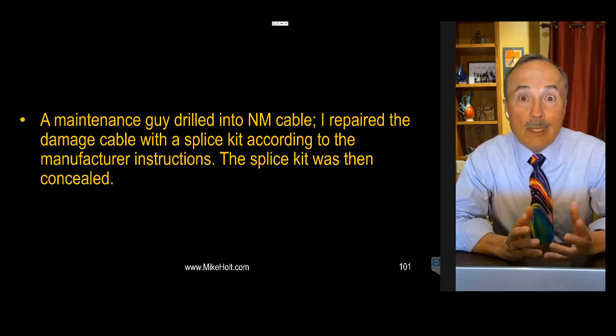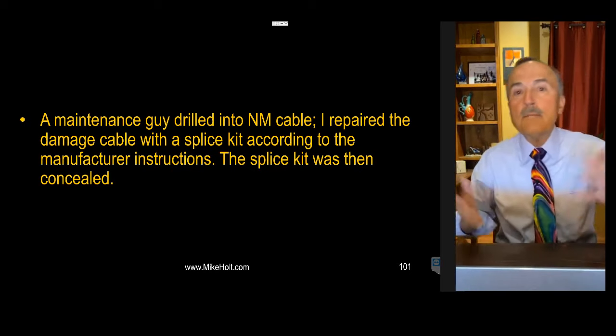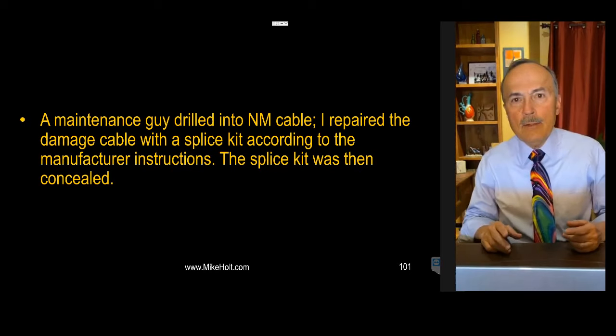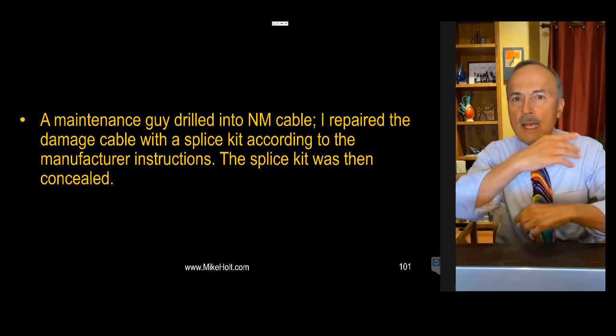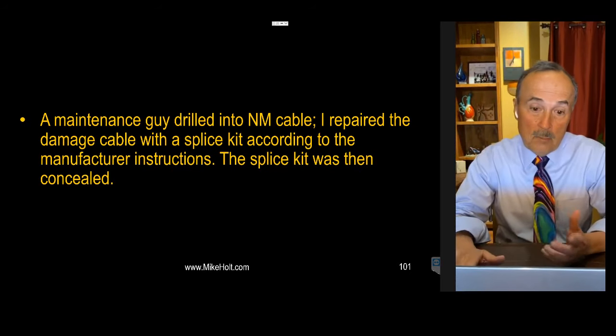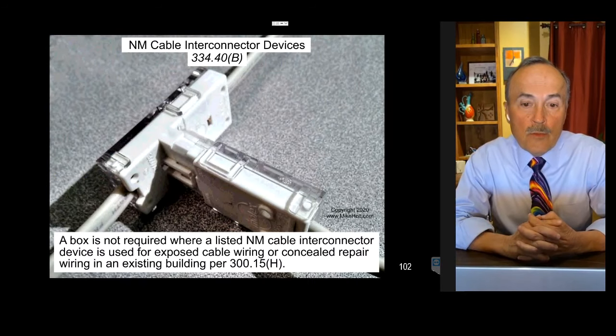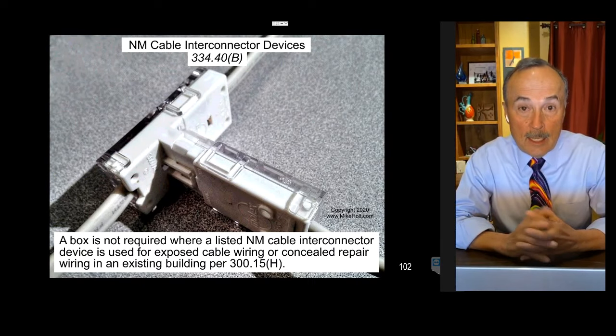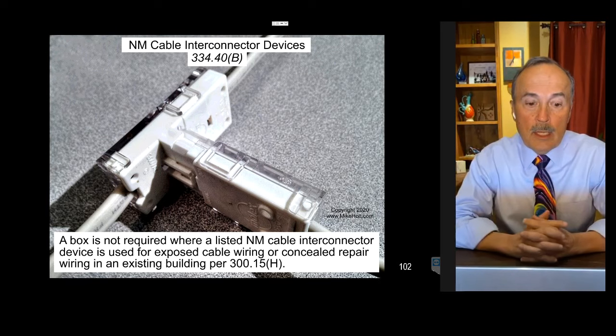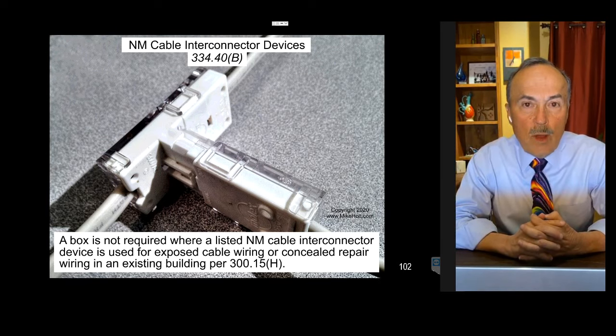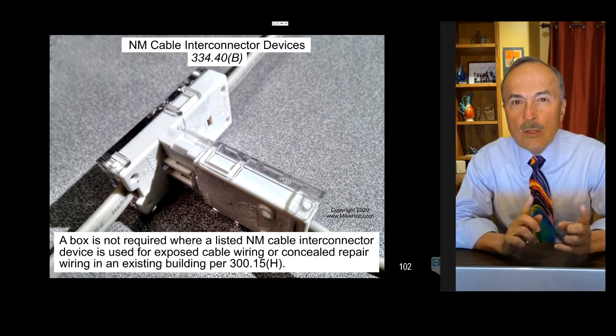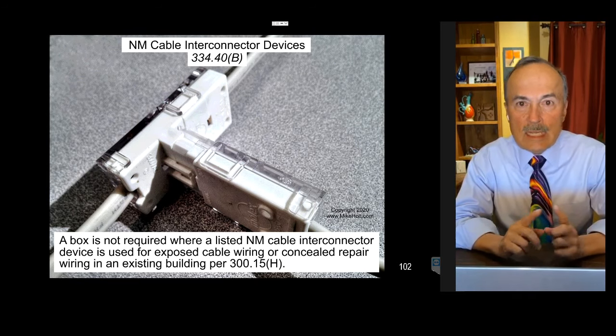This has to do with Romex splice kits. I thought it was an interesting story. Hey, Mike, a maintenance guy drilled into the Romex cable, the NM cable. I repaired the damaged cable with a splice kit according to the manufacturer instructions. The splice kit was then concealed. Well, yeah, that's what you do, right? You drill a hole, oh man, you cut the drywall out. You put the splice kit in there, and they go back and drywall it up, and it's fine. I'm like, okay.